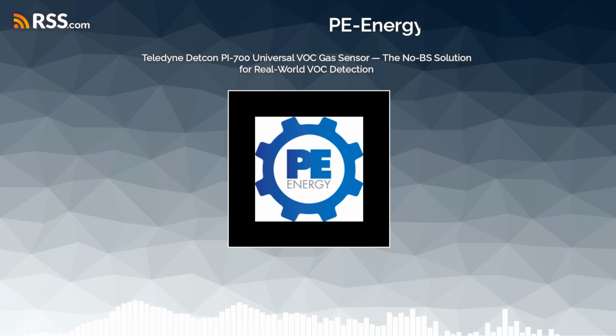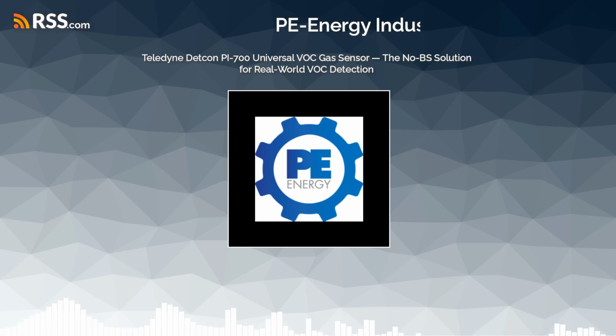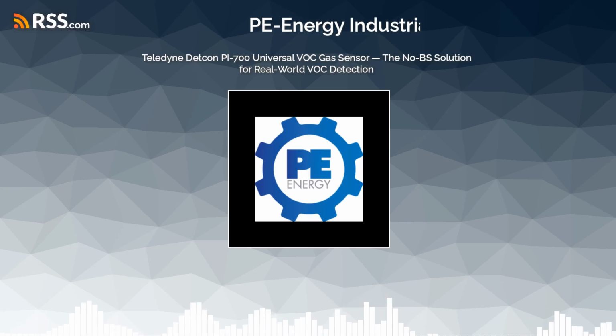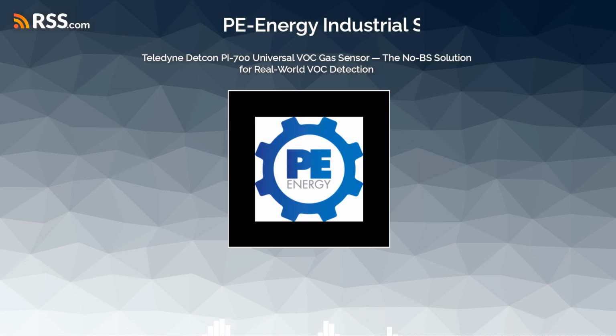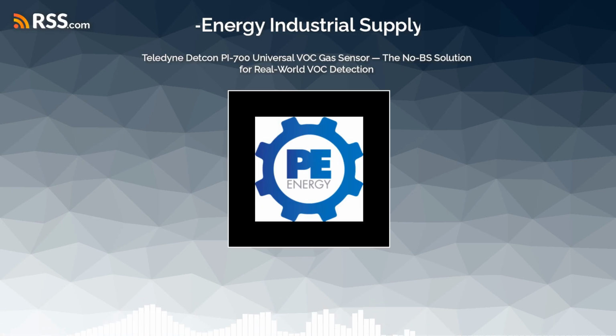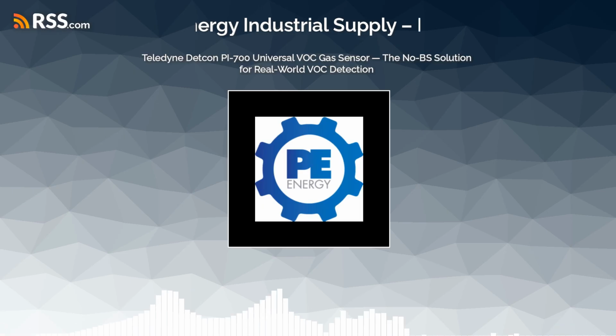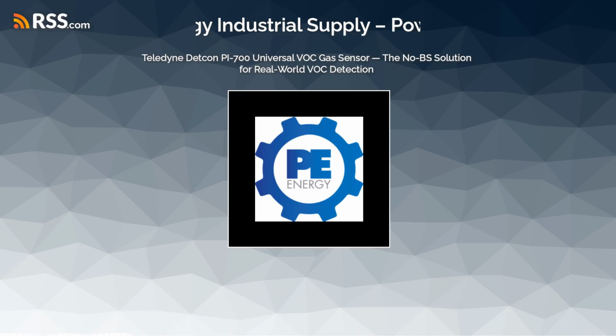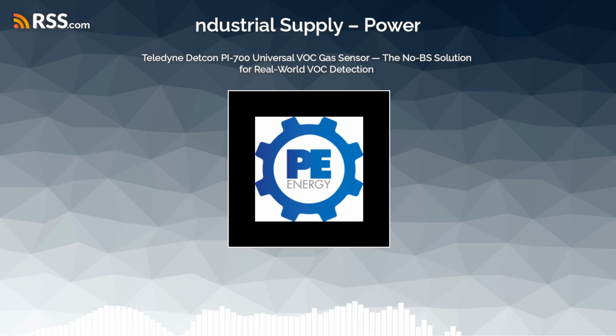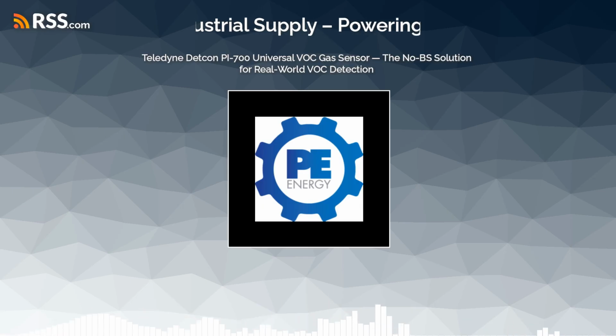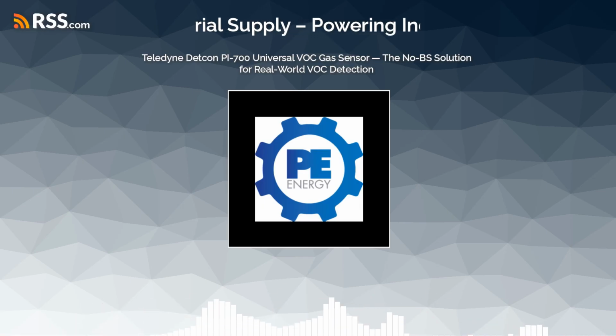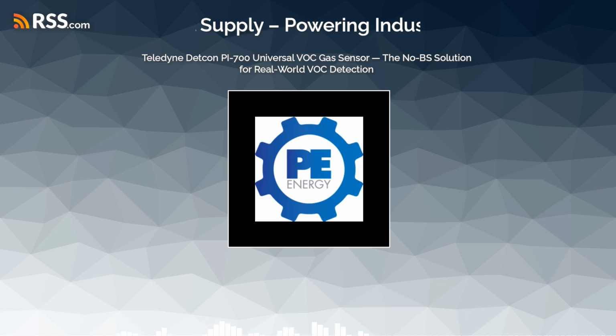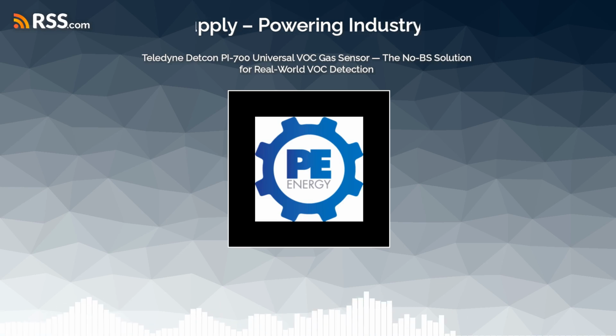They do, and in this context, the bulletproof I/O refers to EMI and RFI immunity. That's electromagnetic and radio frequency interference. So stopping the noise from messing with the signal. Right, because without robust filtering, a technician keying a walkie-talkie 5 feet away could induce a current in the wires that the sensor interprets as a massive gas spike. Oh, wow. So the radio causes a fake gas leak. Exactly. That leads to false alarms.